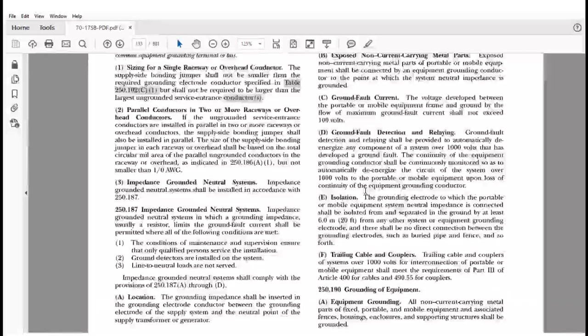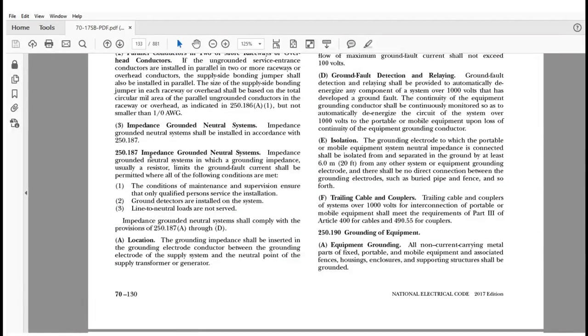Now, I want to go back down and let you see what we're talking about here, and that is dealing with impedance grounded neutral systems, okay? These are systems that aren't directly solidly connected to earth. However, they create a reference due to an impedance device like a resistor. And it can be a high resistor or a low resistor, low impedance, higher impedance, depending on the size of the resistor. Obviously that constitutes which system we're dealing with. It's trying to give you some of the benefits of a system that is theoretically ungrounded but gives you this resistance. But it's called an impedance grounded neutral system.